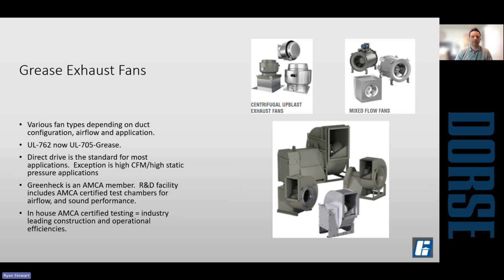So as far as exhaust fans, there are various types, depending on the application. For your typical standalone restaurant with a straight duct run, you're going to see upblast fans. In applications where you have more extensive duct runs, or potentially duct going up a fire shaft, you might see something like a utility set fan. And then in some applications, you end up with some type of grease rated inline fan. The industry is changing from UL 762 grease rating over to UL 705. Currently it's a dual listing, but you'll start seeing UL 705 grease on the labels on the fans. For the most part, for kitchen ventilation, everything's converted over to direct drive.